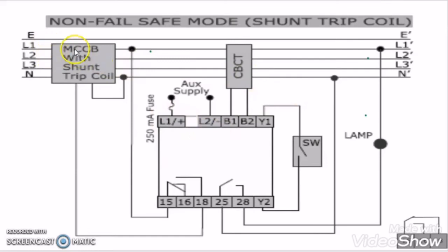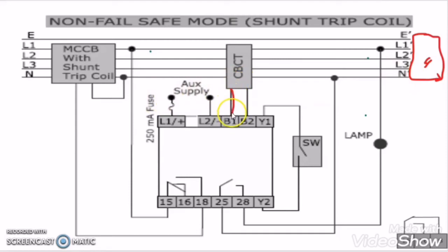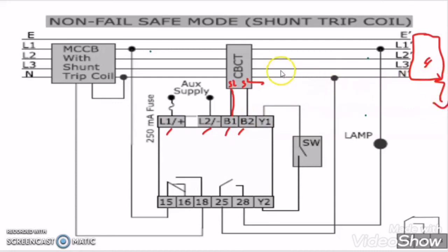Here we have connected one MCCB and the power is coming first to the MCCB breaker. Then the cable L1, L2, L3 — which is R, Y, B — and neutral is passing through the CBCT, and then it connects to the load which we need to protect from any earth fault current. The output of CBCT from the S1 and S2 terminal is connected to B1 and B2 terminal of the ELR in order to have the response from CBCT to ELR. We give power supply to the ELR from the L1 and N terminal or L1 and L2 terminal. Whenever there is an earth fault in the circuit, the CBCT will activate and give response to the ELR.